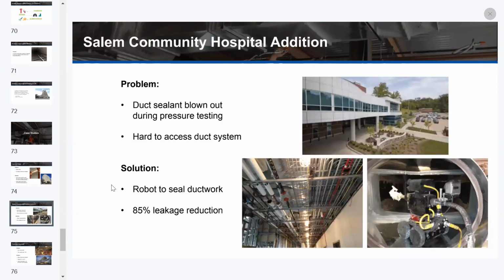Salem Community Hospital. This was a new construction building. Duct sealant was installed and not allowed to cure before install. And also when they made their transverse connections, the butyl gasket on those transverse joints was installed at the very bottom edge, which allowed it to basically squeeze out of that. And when you got into the duct system and looked down the duct system, you could see the butyl sealant hanging. So when they performed the leakage test, many of the joints and seams blew out, causing excessive leakage.